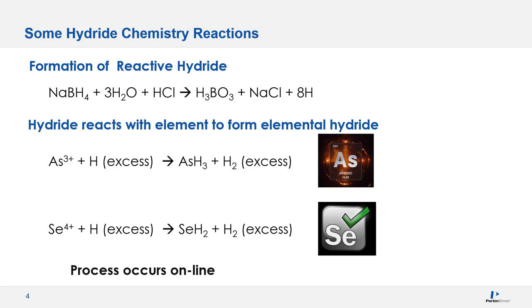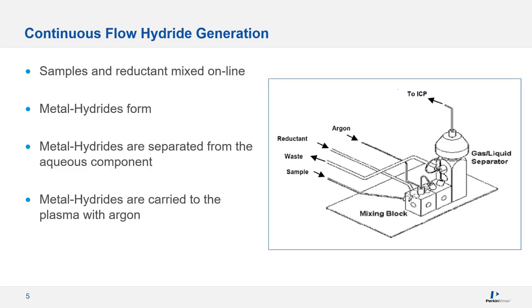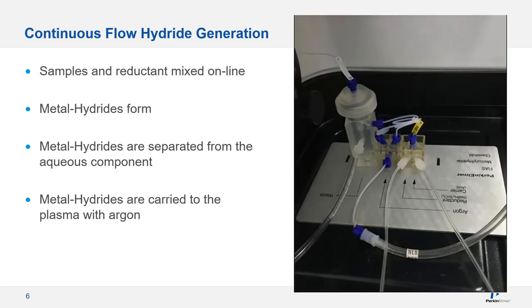To form a reactive hydride, we react sodium borohydride with hydrochloric acid, which forms our reactive hydride in excess. This active hydride then reacts with arsenic-3 and selenium-4 to form arsenic and selenium hydride, which is what gets analyzed in the plasma. When this occurs online, it's called continuous flow hydride generation — samples and reductant are mixed online. The metal hydrides form, are separated from the aqueous component in a gas-liquid separator, and are carried to the plasma while excess aqueous solution is pumped to drain.